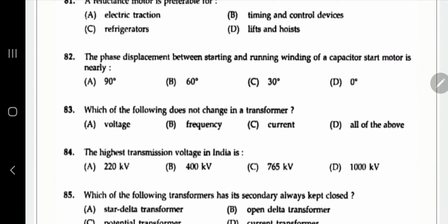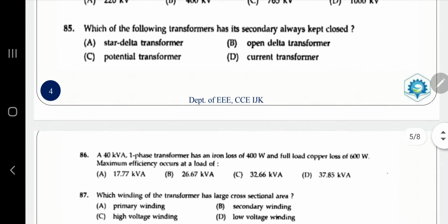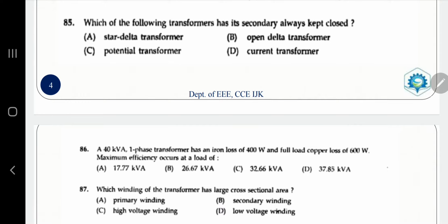Question number 85: which of the following transformers has its secondary always kept closed? The answer is option D, current transformer. The current transformer's secondary side should always be in a closed condition. If it is open, a high voltage appears across the secondary of the transformer. This is because it is basically a step-up transformer, meaning the voltage is being stepped up. So high voltage appears across the secondary, which causes the core to saturate, as well as causing very high danger for the person operating the transformer.